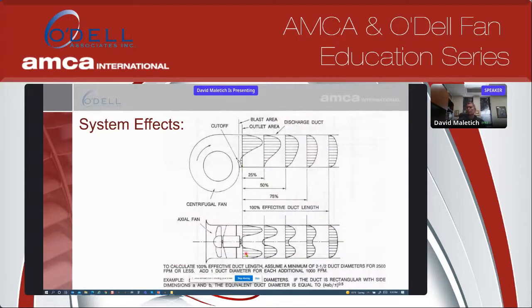If your duct configuration varies from that, it may or may not affect how the fan performs. So for example, on the discharge side of the fan, we always have to remember air has mass and wants to hug the outside of a volute shape or the outside of a housing. So when the air discharges from the fan, it's not uniform. Most of the air on a centrifugal fan discharges at the top part of the housing or the ductwork. At the bottom portion, right behind the cutoff sheet, there can actually be a little bit of a negative pressure region. And it takes 100% of effective duct length for that velocity profile to even out.